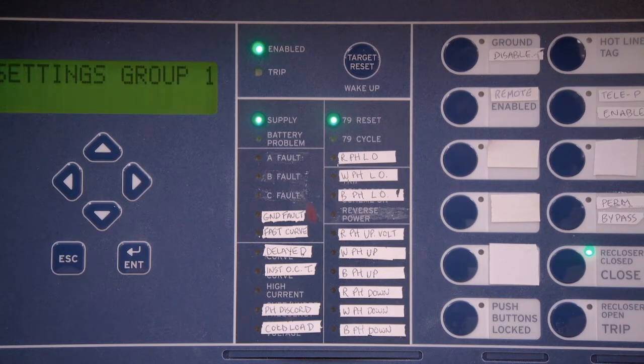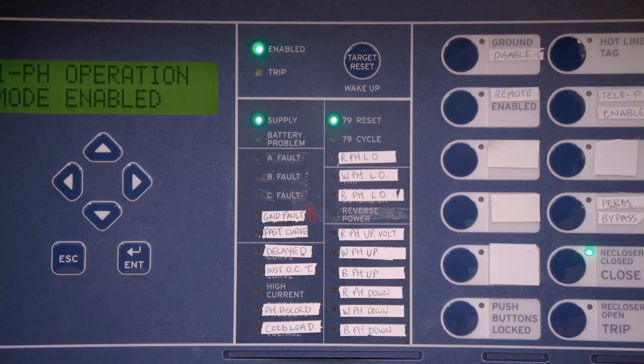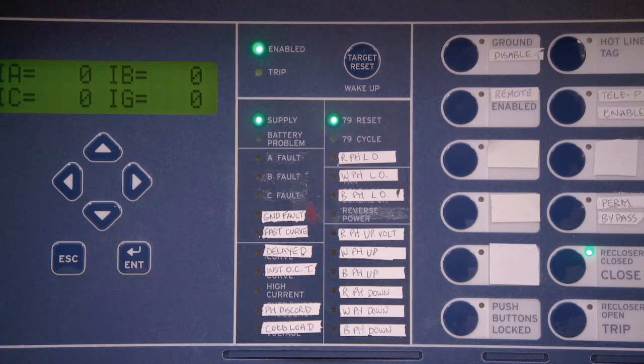The A fault, B fault, and C fault indicators will turn red should a problem occur on those phase reclosers. These could light up in any combination depending on the nature of the fault conditions. Ground fault will indicate that you have picked up a fault on the ground. Since there is not a ground CT, ground indicates an imbalance between phases, such as a high fault condition, phase to ground. Fast curve. This will indicate during the time that the unit is performing a reclosing operation on a fast curve.